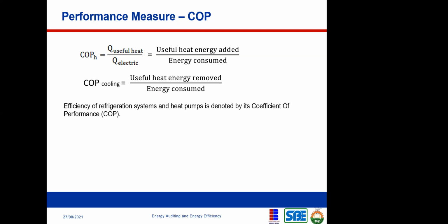Either you're cooling or you're heating. How do we determine their efficiency status? To help us determine the efficiency status, there's what we call performance measures, and by performance measures we mean coefficient of performance. Now this is for heat pumps. We grade the efficiency level based on coefficient of performance.